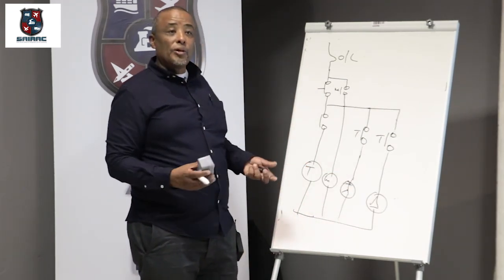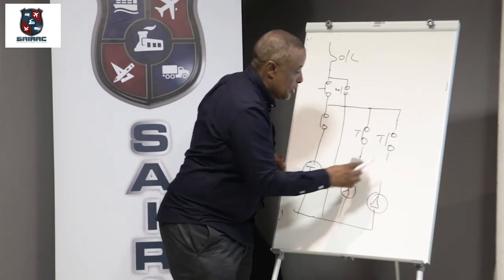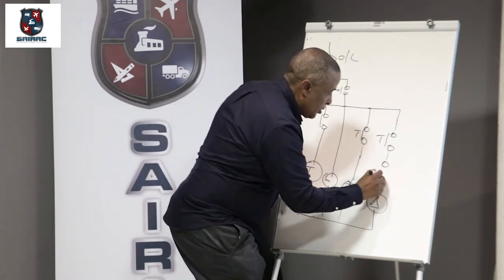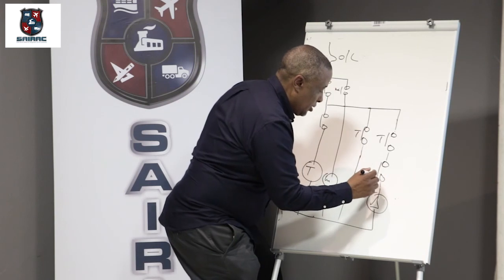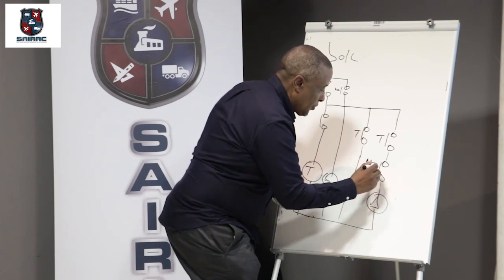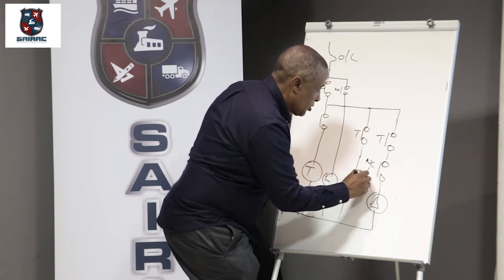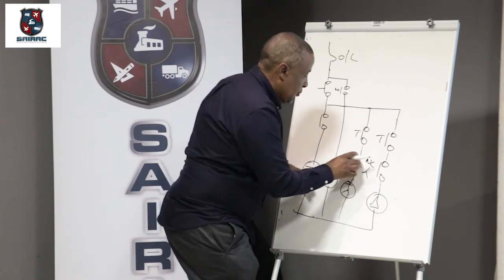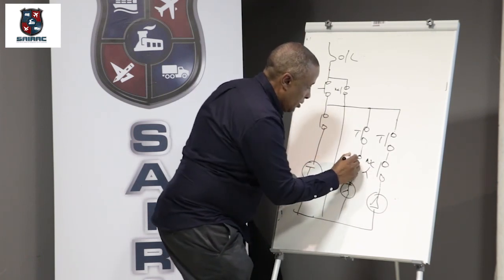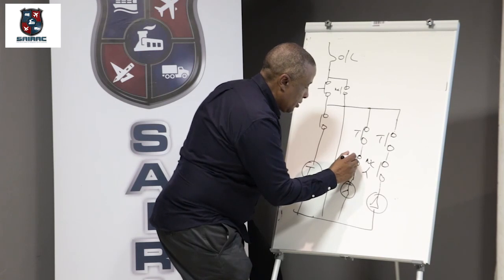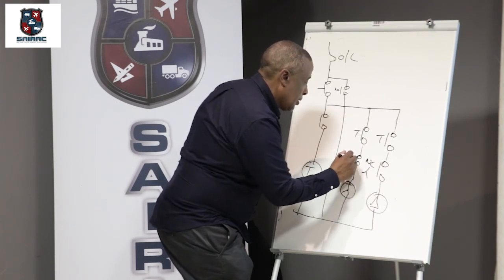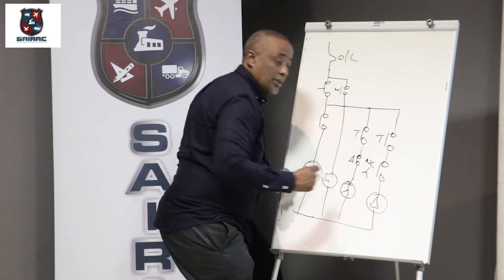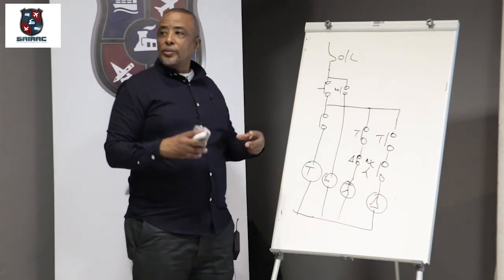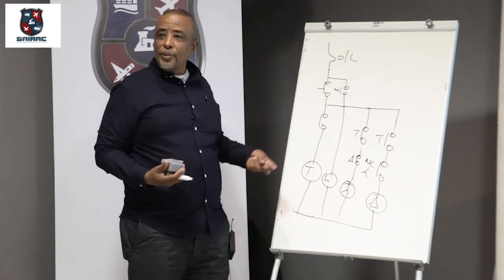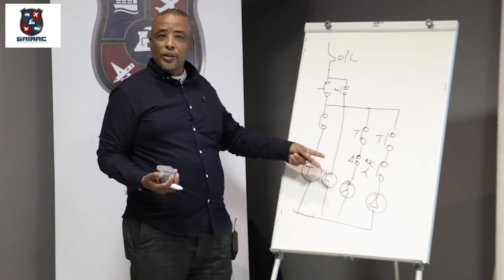To prevent the motor from starting in star and in delta at the same time, we put an interlock. That's the normally closed star, and here we will put a normally closed delta. Okay. Sometimes the interlock is mechanical. Over and above that, we use the electrical interlock.